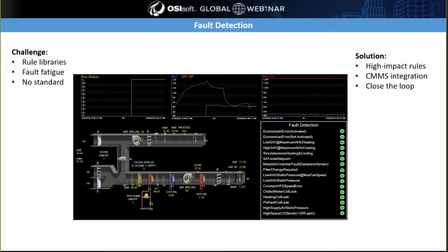And if you walk through the analytic, the temperature probes installed in an air handler, when they're installed, are probably accurate to about plus or minus 1 degree, and they drift over time. They're almost never maintained. So what that means is that there's a strong chance you're going to start creating faults that reflect sensor accuracy and not the true operation of the system. But even if the sensors were perfectly accurate to a fraction of a degree, do you still want to ask somebody to go and troubleshoot why your supply air temperature is 57 degrees instead of 55? And I think the answer to that question is no.